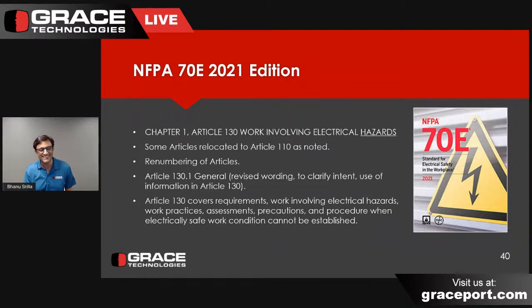Terry, go ahead. Okay, so really Article 130 is clause 4.3 in Z462, and I want to make sure I keep giving that overlay between the 2 standards. This comes back to what Bhanu has been presenting: we had a structural reorganization occur where a lot of Article 130 content was moved to Article 110, and we did that in Z462 as well. We moved clause 4.3 content to clause 4.1, and we did make some changes, though.